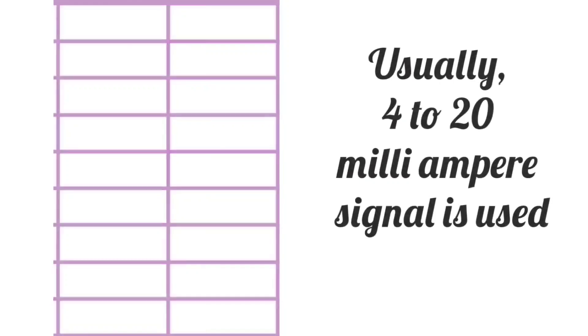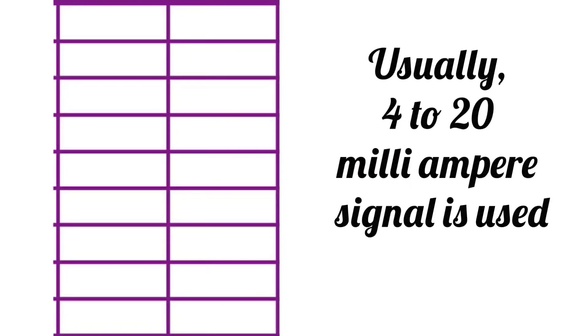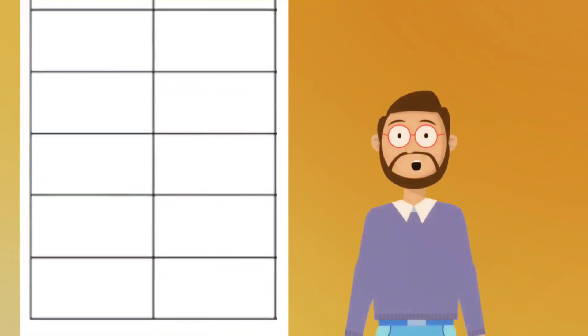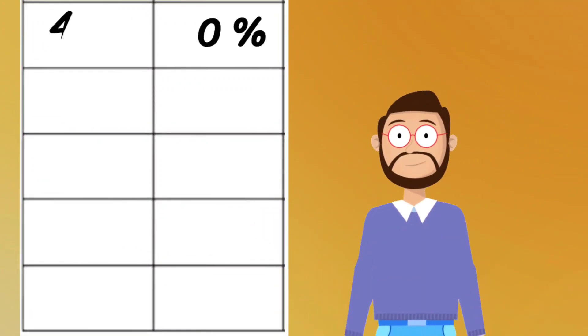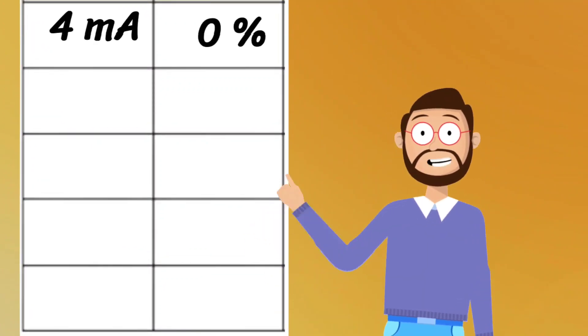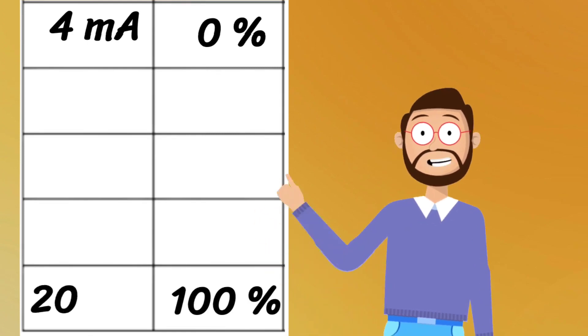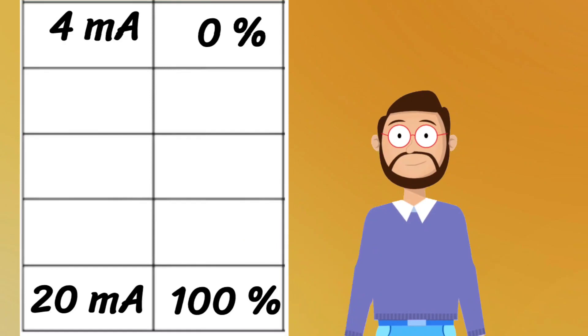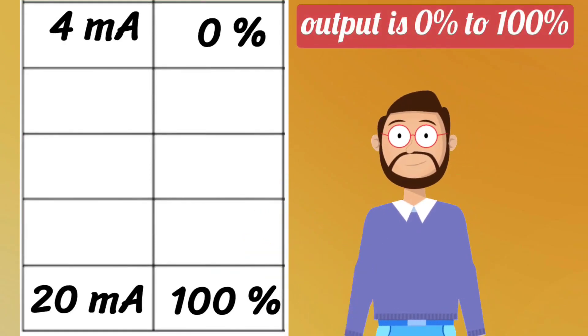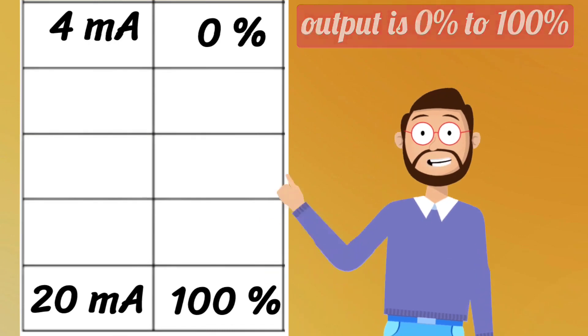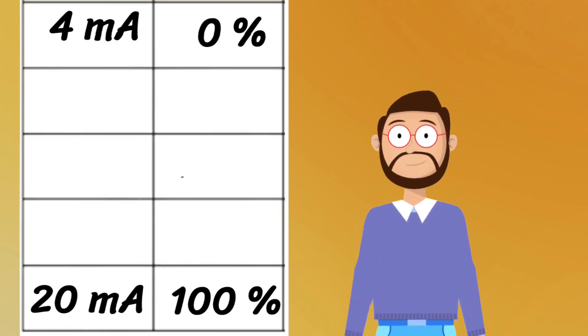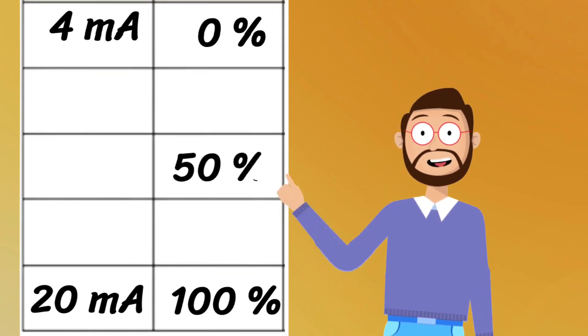Usually, only 4 to 20 milliampere signal is used. So first write 0%, now write 4 milliamperes in front of it. Write 100% in last and write 20 milliamperes in front of it. We did this because the output is 0% to 100%.